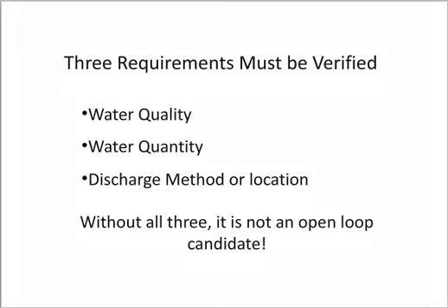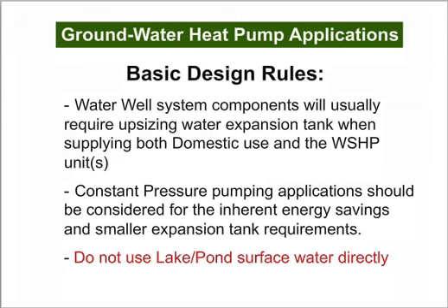So the three absolute must requirements that you as a contractor, designer, engineer, architect must verify, whoever's looking at proceeding with this project, is basically kind of like three legs to that stool that have to be answered. Do you have good water quality? Do you have good water quantity? And what is going to be the discharge method or that location? If you can't successfully apply a yes, or if you can't satisfy all three of these, you don't want to proceed with it because you certainly don't want to have a bad application out there.